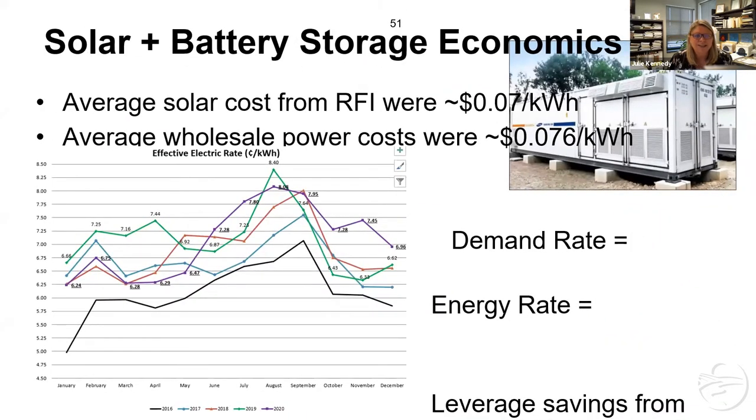Through our RFI with Jill Clyburn and Associates, we were seeing numbers in the $70 per megawatt-hour — the equivalent of 7 cents per kilowatt-hour — for solar coming in, and our average wholesale power supply was right about that. The return on investment for subscribers was significantly longer than the 10-to-15 years they wanted — numbers were showing 20 to 25 years. Our energy rate from Minnesota Power was quite low at 2.6 cents per kilowatt-hour, and it was tough to overcome those energy costs for solar. But where we really saw the ability to pull a battery in was on the demand rate — at that point it was $19.48 per kilowatt per month. That was a significant portion of our bill. At 31 megawatts summer peak, that's $500,000 to $600,000 each month just for that 15-minute peak hit one time throughout the month.